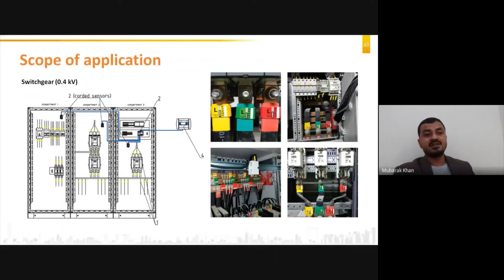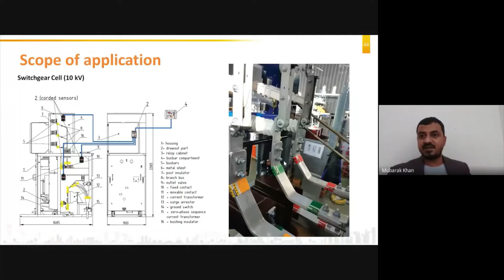This is a 6.6 kV, 11 kV type of panel where we have a high voltage circuit breaker. There will be an incoming cable compartment, circuit breaker compartment, and metering compartment. So we will use one multi-channel FPA, place sensors in different compartments, and place stickers on all the joints, and then we can monitor the one circuit breaker panel with a single FPA.